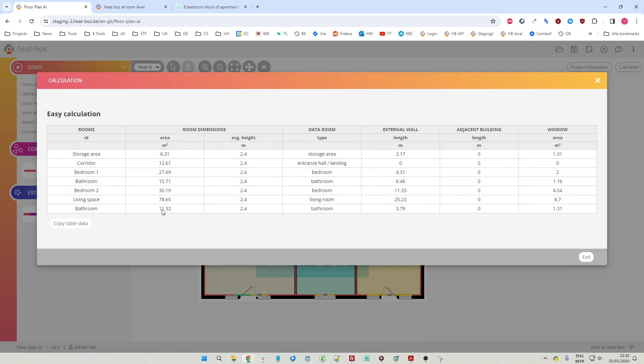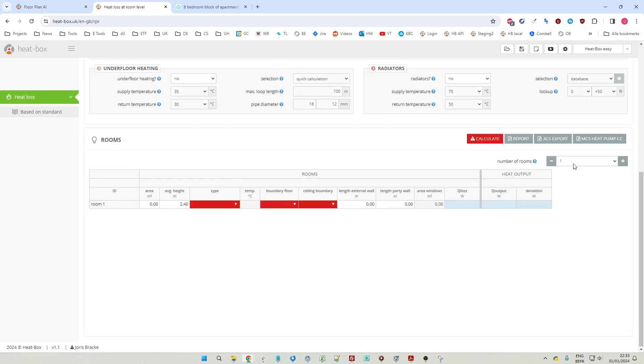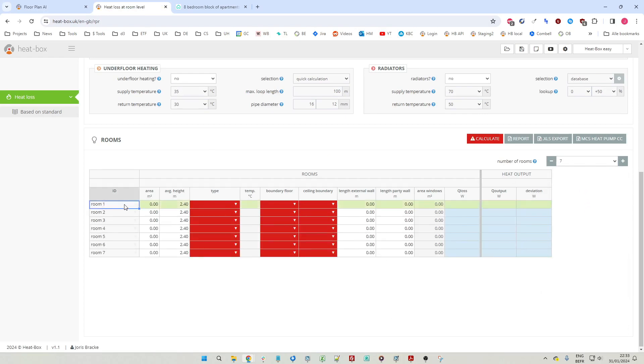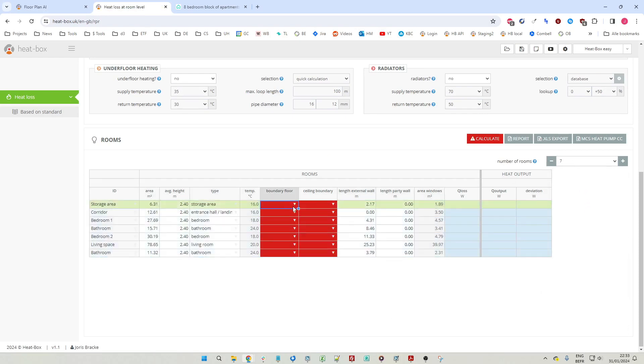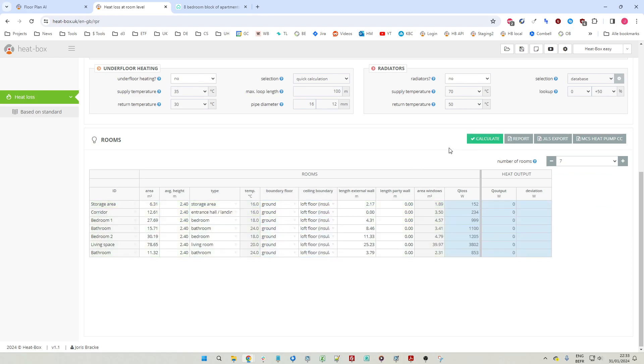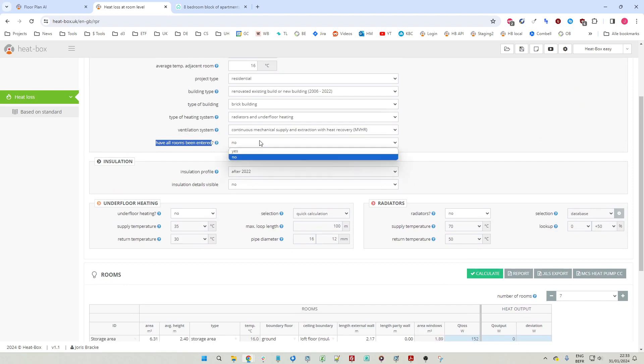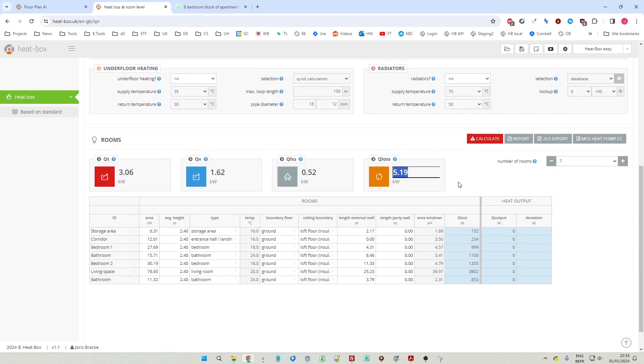We press the calculate button and we have all the dimensions for the different rooms - seven rooms in total. We can copy all the data, go to the calculation at room level, say we have seven rooms, and paste our data. The boundary to the floor is ground floor and the ceiling boundary is loft floor. We draw down both cells and press calculate. Here we have the heat loads at room level, and if all rooms of the building have been entered, we also see the heat loads at building level. This way it's much easier and faster to do your heat load calculations.